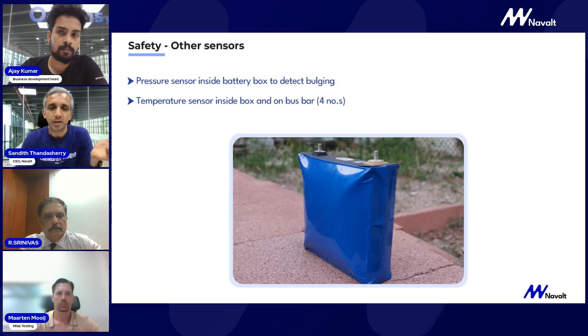Additional sensors, like pressure sensors to detect whether the battery itself is bulging, and temperature sensors inside the box as well as on the bus bar — these are certain things we also do by practice. There is, of course, a fire protection requirement from the class side too, whether it's A60 insulation on the battery room itself, or fixed and portable fire systems, etc.